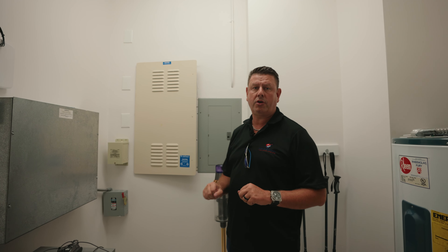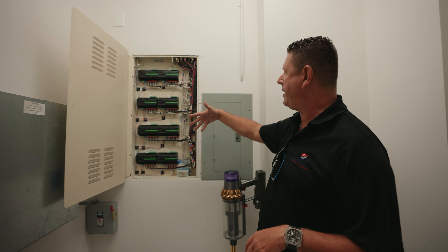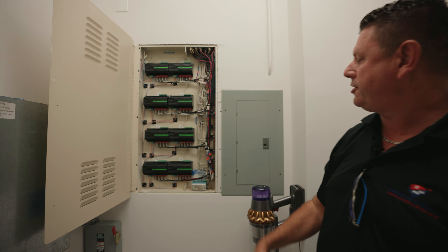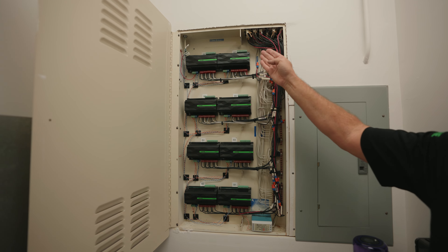We're in one of the utility rooms in this home. This home had three panels throughout the house. We kept the original panel, took out some of the supports that the old modules were in, and installed Loxone 4-channel dimmer modules. In this particular instance, we've got eight of them, utilizing all the existing 110-volt wiring going into the Molex connectors.